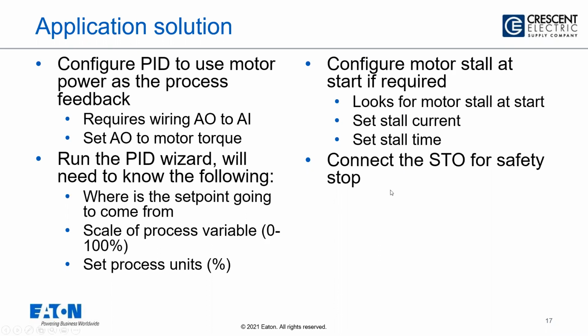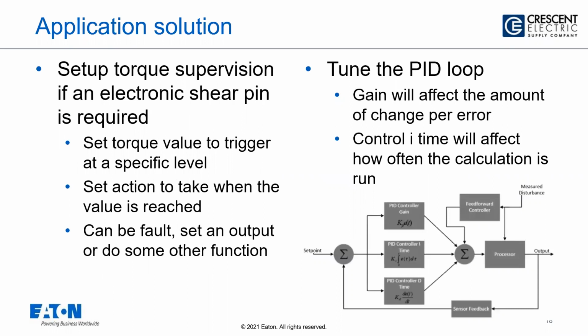Next one, please. And the application, how do you set up? Again, set up torque supervision, and there is an electronic shear pin. In case the motor torque exceeds a particular value, the drive can take an action, whether it is a fault indication or to do something like a trip. So with the self-monitoring capability within the drive, you can make sure that the torque is sensed and then take the necessary action in order to protect your application or alert the user or maintenance team.